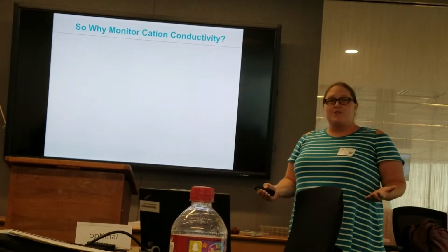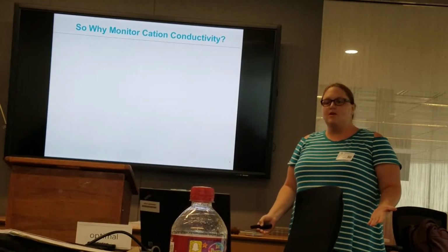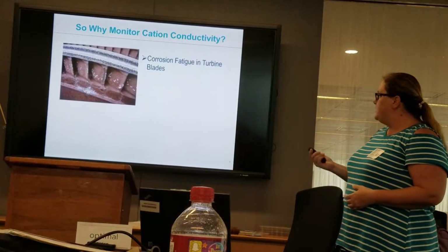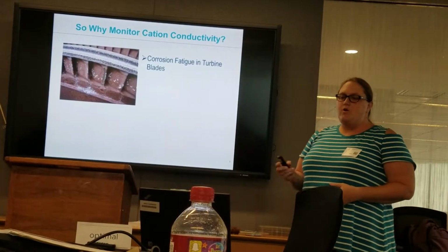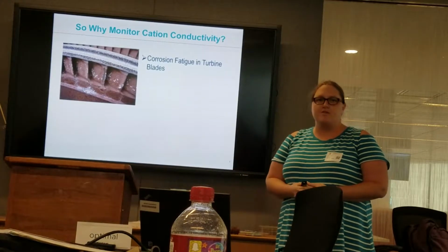Now, why do we monitor cation conductivity? Past experience, we know that these contaminants actually cause problems in our turbine blades. It causes corrosion fatigue. But not only that, cation conductivity, the main purpose is to monitor these chlorides and sulfate.